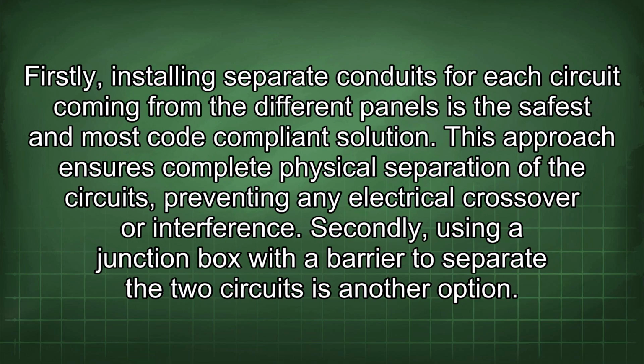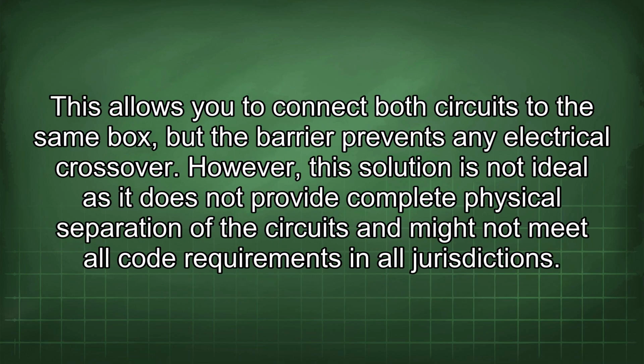Firstly, installing separate conduits for each circuit coming from the different panels is the safest and most code-compliant solution. This approach ensures complete physical separation of the circuits, preventing any electrical crossover or interference. Secondly, using a junction box with a barrier to separate the two circuits is another option. This allows you to connect both circuits to the same box, but the barrier prevents any electrical crossover. However, this solution is not ideal as it does not provide complete physical separation of the circuits and might not meet all code requirements in all jurisdictions.